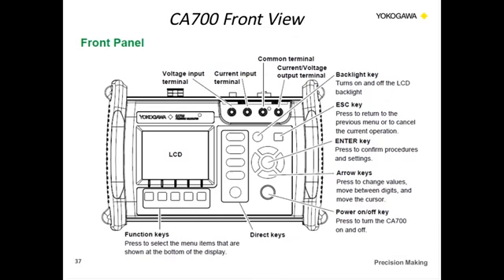So the CA700, here is a front panel view of the unit itself, and we'll talk about the direct keys in a slide or two later. The function keys on the left, depending on what mode you're in, let you change the display settings and change the units. The terminals on top are where you hook up your terminals to your device. You can measure and source current and voltage. You also have the ability to power a device via loop power. There's also a built-in 250 ohm resistor that can be turned on and off, and we'll talk about that later. Then there is a backlight key that turns the backlight on for the display, the escape key to go back, and then the arrow keys and the enter key for navigating the different menus. There's also the bottom button on the right, which is the power on and off key. When you power it off, it'll confirm that you want to turn it off.